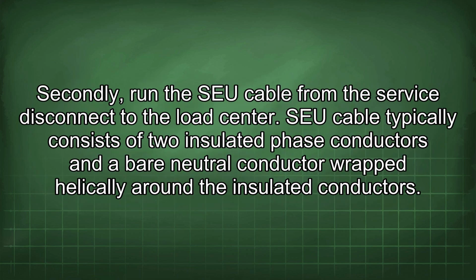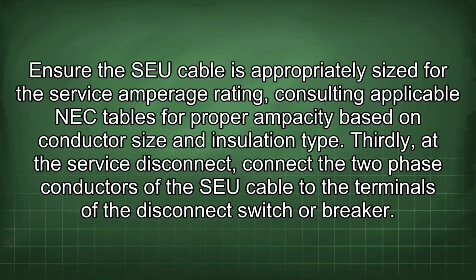Secondly, run the SEU cable from the service disconnect to the load center. SEU cable typically consists of two insulated phase conductors and a bare neutral conductor wrapped helically around the insulated conductors. Ensure the SEU cable is appropriately sized for the service amperage rating, consulting applicable NEC tables for proper ampacity based on conductor size and insulation type.